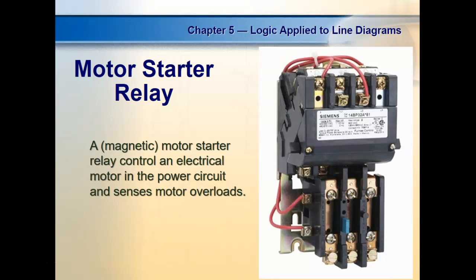Okay? Just like your car, right? Whenever you first start it up, it's sucking up the gas. It's trying to turn itself over, and it takes more work for it to start. Right? Kind of like what takes more work for you to start. Taking that first step or continuing walking. Which one takes more energy? Taking the first step. Getting up off the couch and taking the first step. Same thing for a motor. Taking that first step, getting up off the couch, takes it a minute. So it pulls excessive current for that 1 minute. That's fine. But continuing to pull it causes a lot of problems down the road. So we have these guys in line with the motor contacts to prevent overload.